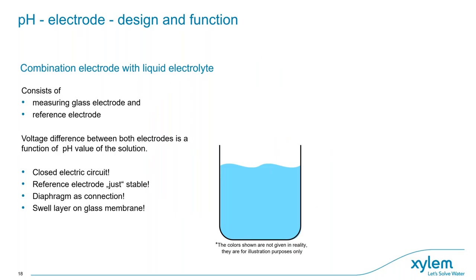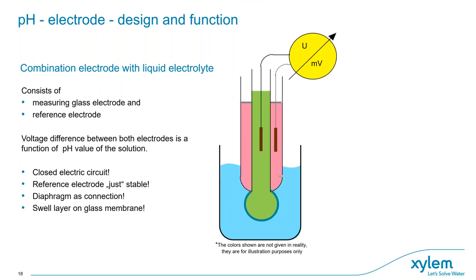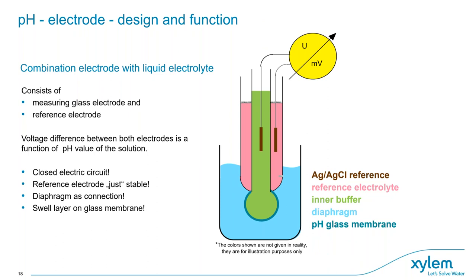Now we come to an important point about how the electrode works. A pH combination electrode consists of the measuring glass and the so-called reference electrode. We want to measure exactly and only the pH-dependent potential created at the glass electrode. On the surface of the glass electrode is the important swell layer — provided it has been stored long enough in water or electrolyte. The more H+ ions are in the solution, the more positive the potential at this swell layer. We cannot simply measure this single potential alone.